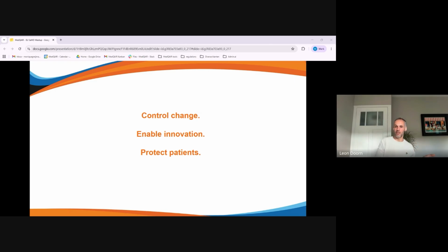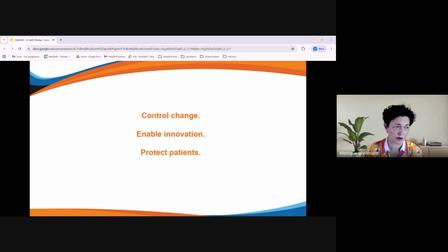What do you prioritize? Quick release to address an urgent issue in the field, and maybe skip a little bit on the verification and validation tests, versus going through your validation and verification test cases to the full extent, realizing there's an issue in the field. Also there, you need to understand what the criticality is for the patient in the end. That's what you need to assess again and again in each of these situations. If the patient can be impacted on short notice with these types of issues, then you need to act, or you need to contain.